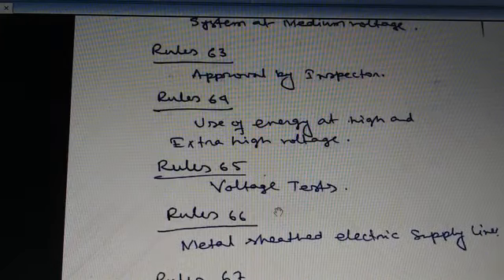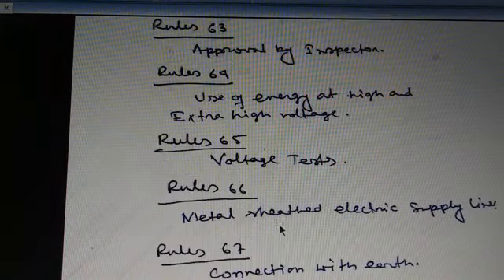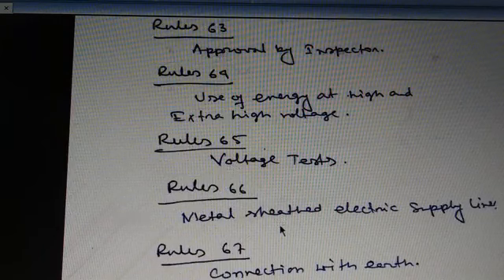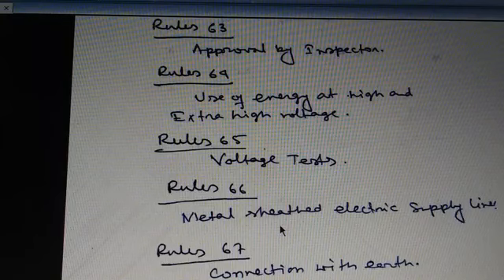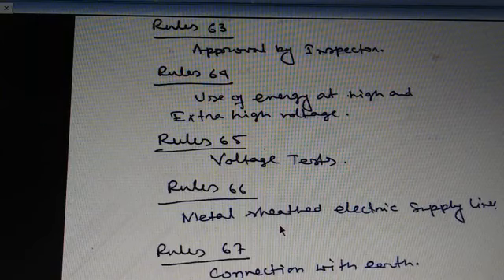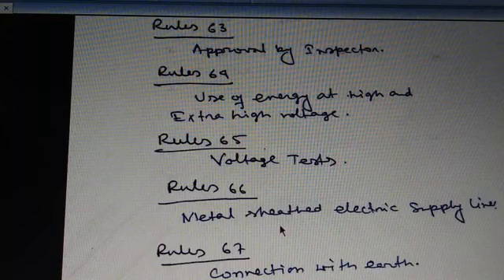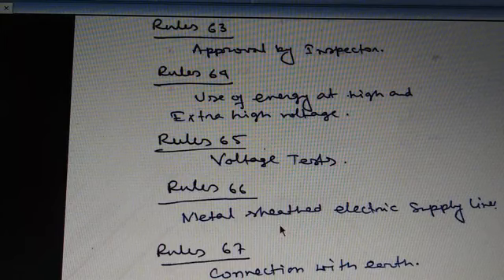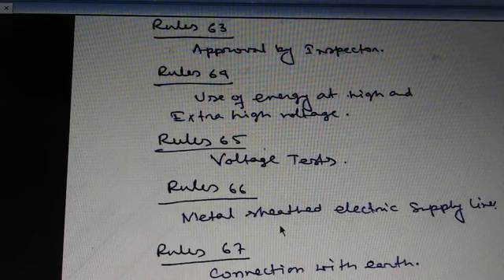Now, the supplier shall duly record the result of every test made under these rules. Now, rule number 66. Rule number 66 is related to metal sheathed electrical supply lines. The following provisions shall apply to electrical supply lines of the supplier for use of high and extra high voltage. First point, the conductors shall be enclosed in metal sheaths which shall be electrically continuous and connected with the earth.